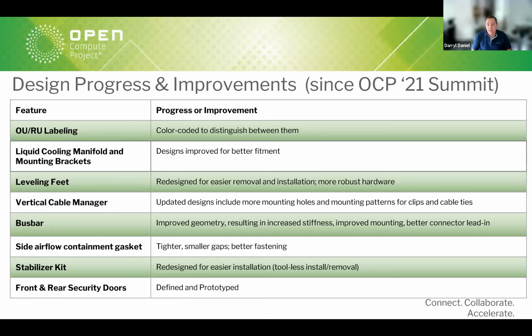On the bus bar, we also made some changes from the previous design. The geometry of the bus bar itself has been improved, resulting in increased torsional stiffness in the overall design. We've improved how it mounts to the rack, in terms of the hardware we're using, and we've increased the chamfer lead-in on the bull nose of the bus bar to help with mating of the IT gear connectors as they engage with that bus bar.